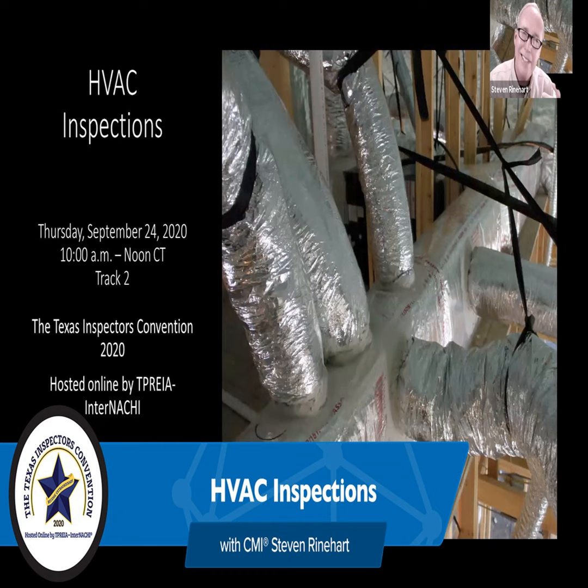although the evidence could have been a previous leak, and I don't know if anybody goes the trouble of cleaning rust or scale out of a secondary pan. But if you're there in off season and you see evidence, you can see a water line where it was in the pan. You don't know. It's kind of like you see a ceiling stain and it's not wet, but it hadn't rained in a month. You don't know if that leak is active. You're not going to be there to run the air conditioner long enough to know if it's got an issue. And that's why the water stains in the pan.